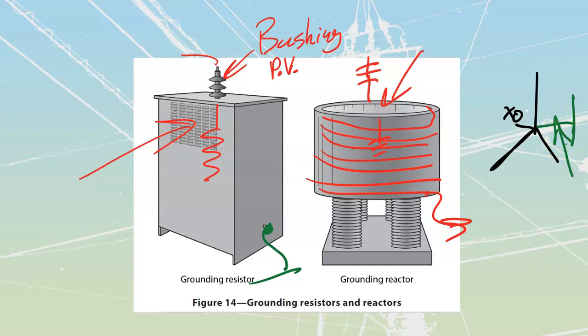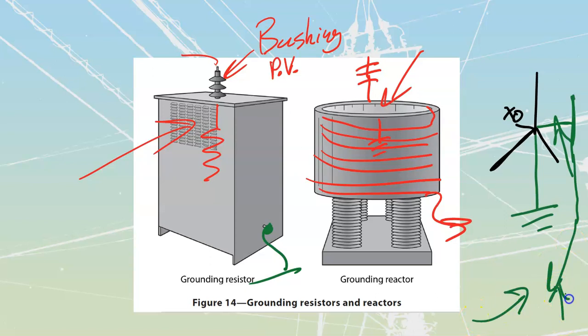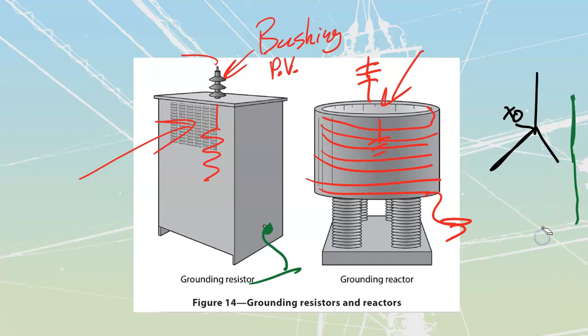If you've got a Y system where you're going to have the actual grounding at the transformer, so I place my ground plate over here at the transformer, connected over to my XO point, then I'm going to have my bonding connected to the can, and everything else through the rest of the system is all going to bond back to that same can over there. That's when it could be allowed. However, if I've got my Y system grounded at the actual service box, then I'm going to have to remove that one from it.